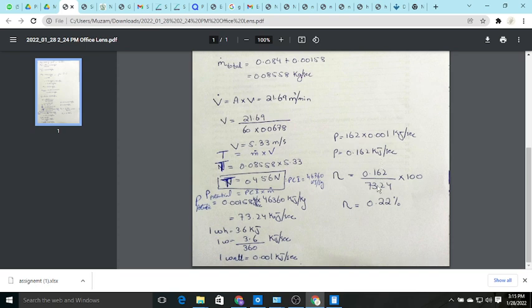Dividing output by input, we have only 162 electrical power and 73.25 kilojoules per second we are burning in the fuel. So we get only 0.22% of electrical power after burning. It is very low efficiency because it is not designed for a gas turbine system.